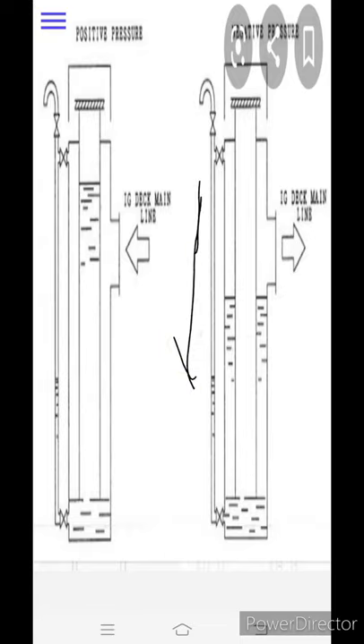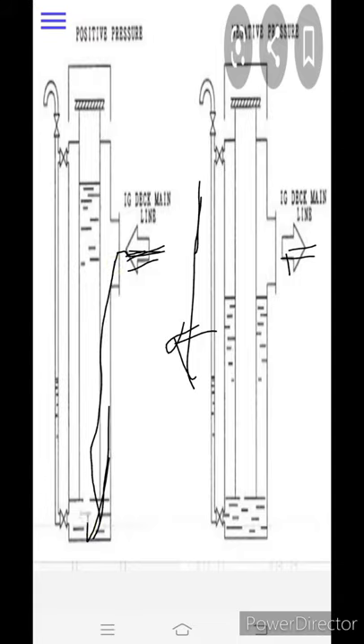This is a gauge glass, which is used to measure the water content in the PV breaker. The liquid inside is not pure water — it is water mixed with glycerin. This area is connected to the IG main line. Whenever there is excessive pressure in the tanks and the PV valve is not able to cope, the excessive pressure comes into the IG line, travels to the PV breaker, and pushes all the water out through the upper area.